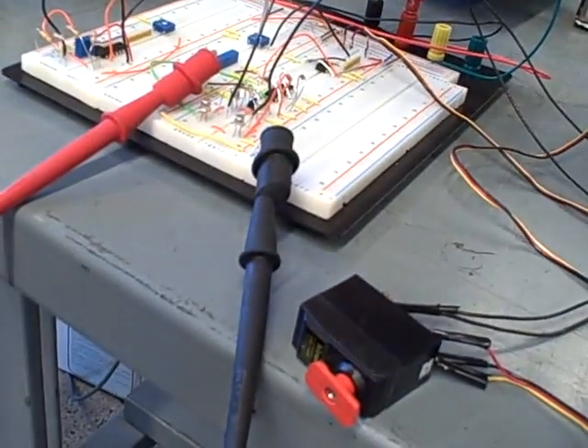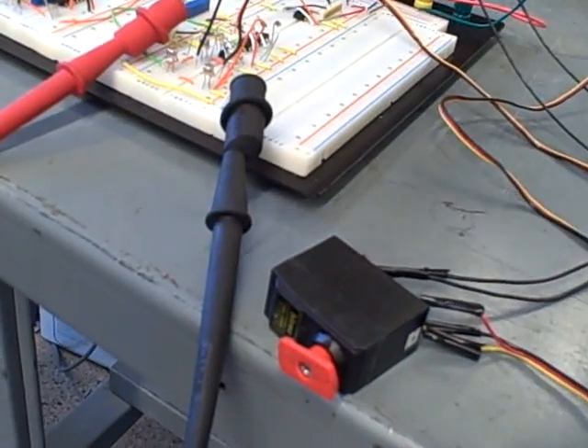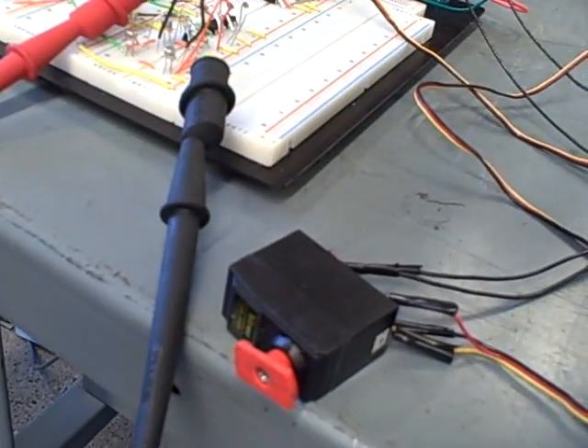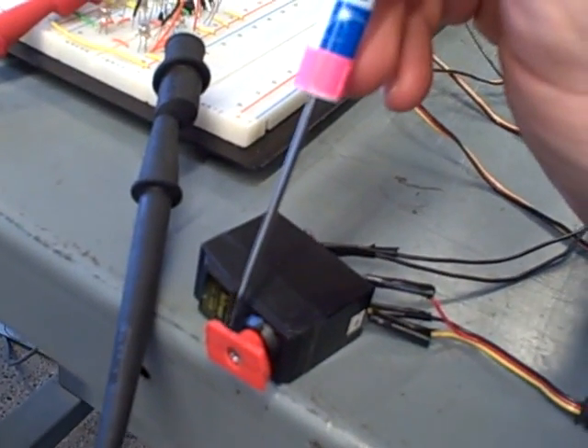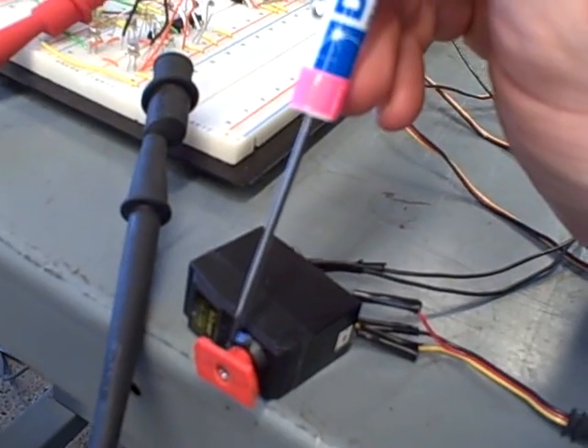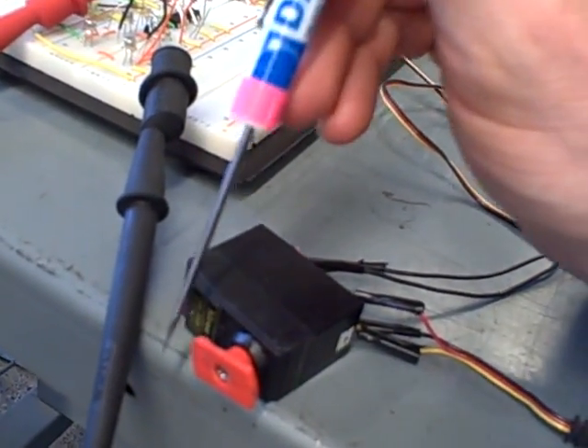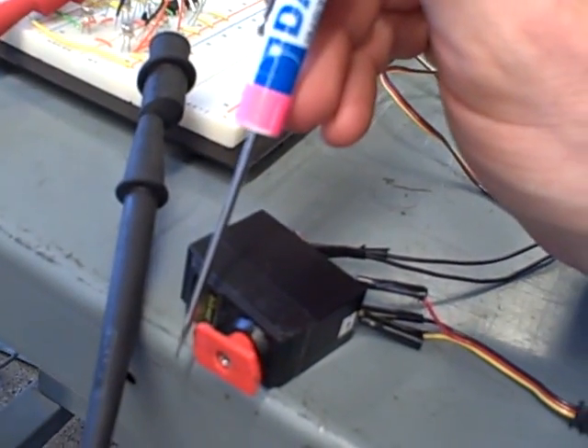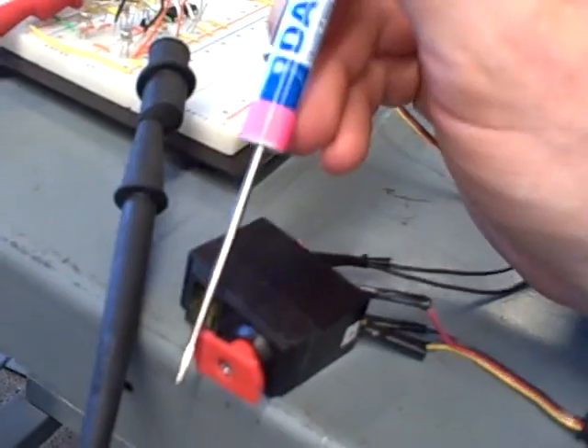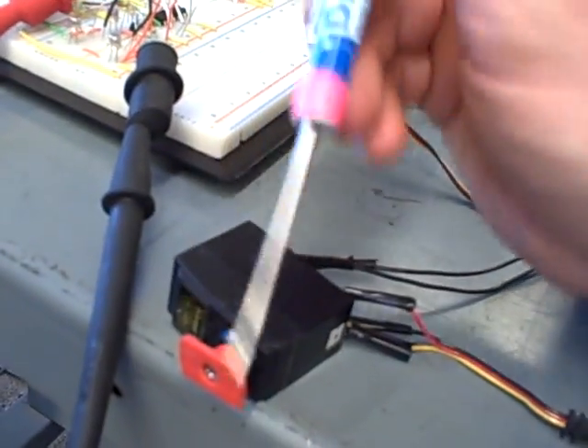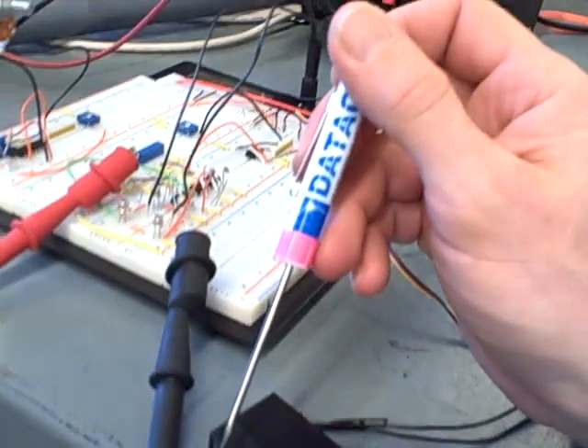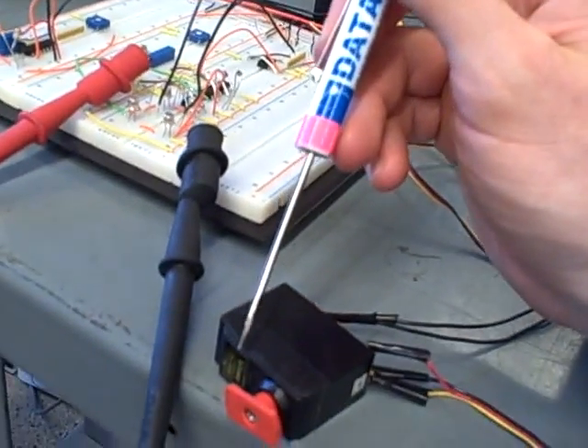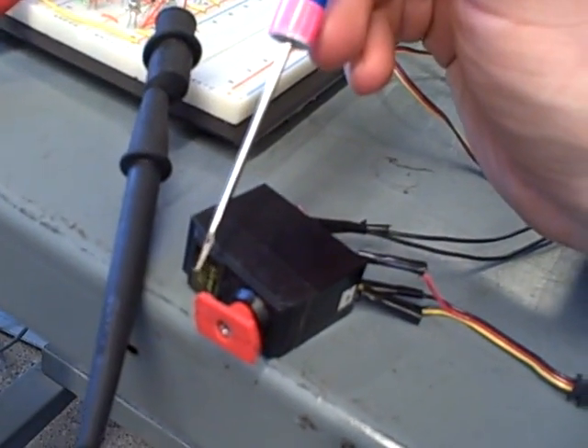Now the risk in having too small of a deadband is that if your deadband isn't large enough, the coasting action of the motor will carry it past where it needs to go. It will overshoot, and then the valve goes back, and then it goes forth, and back and forth, and just hunts. And that's a problem we haven't encountered yet in this design, but potentially we could.